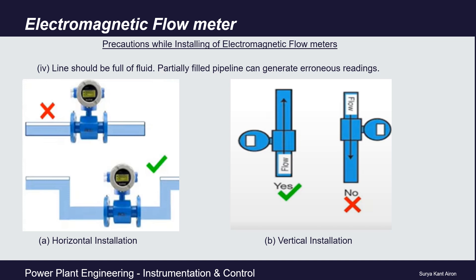The third requirement is that the pipeline must be fully filled. In the case of a partially filled pipeline, the measured output will be incorrect. Thus, during horizontal installation, electromagnetic flow meters are installed with a U-shaped arrangement so that the line is always fully filled at the cross-section where the flow meter is installed. For vertical installation, the flow should be from bottom to top.